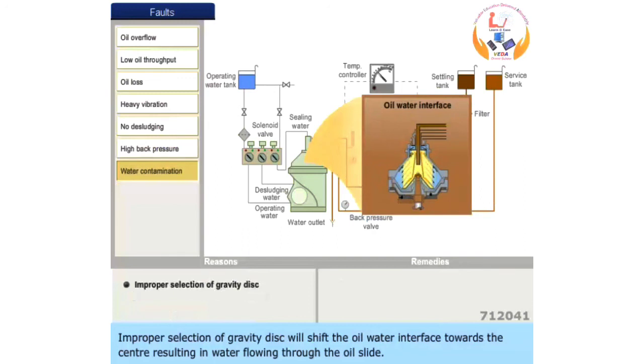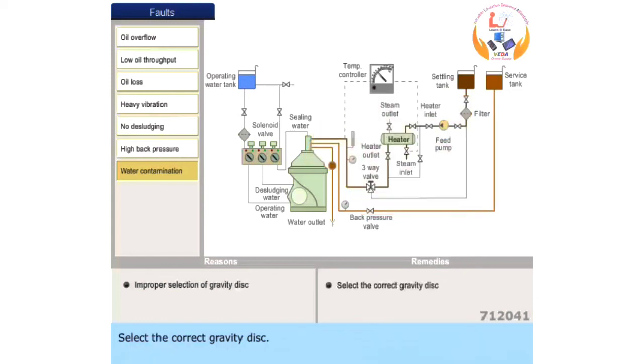Improper selection of gravity disk will shift the oil-water interface towards the center, resulting in water flowing through the oil slide. Select the correct gravity disk.